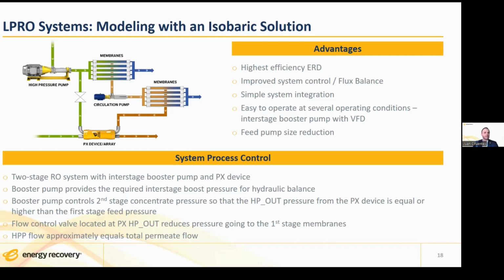Which are the advantages of this system? We are using the highest efficiency ERD. We improve the control and the balance of fluxes of the system. It is a very simple integration, just a pump and the PXs. And also, we can operate in a wide range of operating conditions because the PX can operate in a very wide range of pressures and flows with a very low impact on the efficiency. Finally, we are reducing the high pressure pump size.